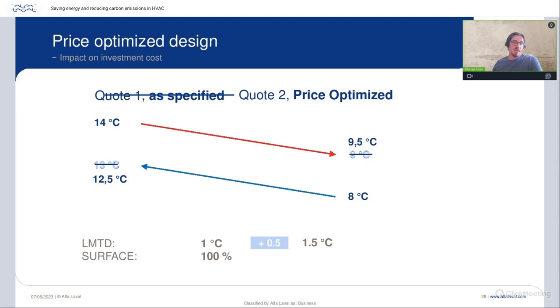So if we look at the typical optimization of using these tolerances, instead of having 9 degrees, you will get 9.5. On the cold outlet, you will have 12.5. So this is half a degree. At the bottom, we see we get an LMTD of 1.5 instead of 1. So the average temperature difference between the hot and the cold side is now 1.5 degrees.